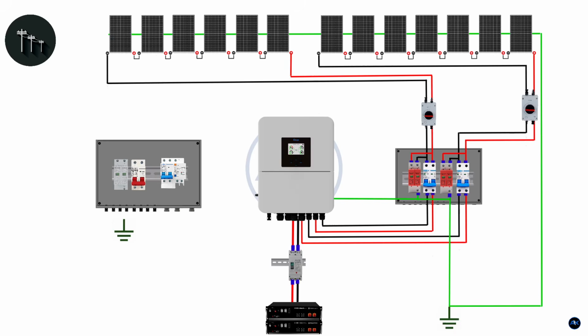Connect your battery bank to a main DC breaker, sized appropriately for your battery current. Run the main positive and negative battery cables from this DC breaker to the battery input terminals on your hybrid inverter. Ensure correct polarity.